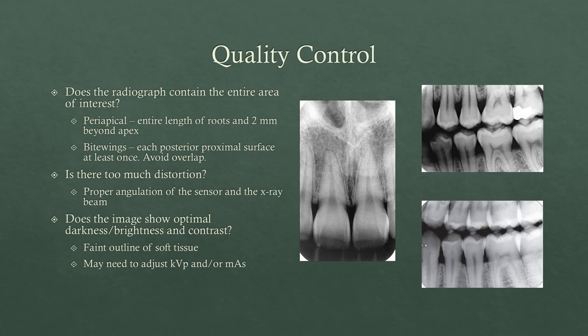You also want to look at the overall image brightness and darkness to differentiate between enamel and dentin. This lighter line is the enamel around the tooth — it has more mineral, it blocks more x-rays, it attenuates more, making it appear lighter in your radiograph. If you don't see that distinguishing line between enamel and dentin, you know there's something wrong with your contrast or brightness. You might need to adjust KVP or MAS. Usually all we can change is the time, so we increase MAS by doing a longer exposure time if it's too light, and shorten the time if it's too dark.